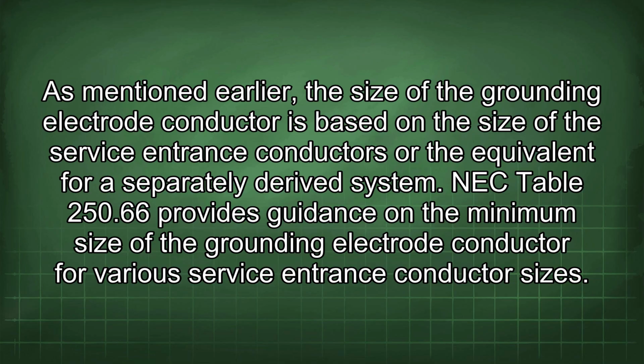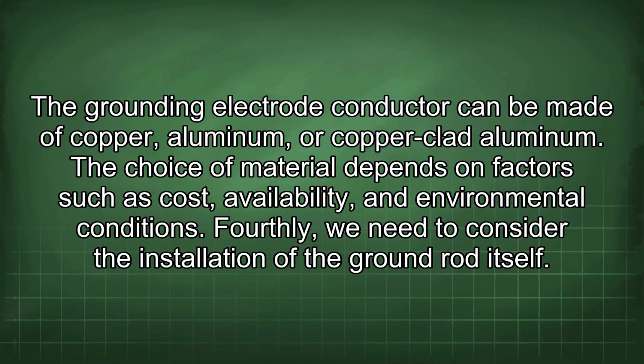Thirdly, it is important to consider the size and type of grounding electrode conductor. As mentioned earlier, the size of the grounding electrode conductor is based on the size of the service entrance conductors or the equivalent for a separately derived system. NEC Table 250.66 provides guidance on the minimum size of the grounding electrode conductor for various service entrance conductor sizes. The grounding electrode conductor can be made of copper, aluminum, or copper-clad aluminum. The choice of material depends on factors such as cost, availability, and environmental conditions.